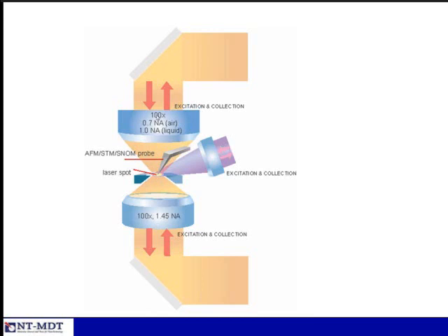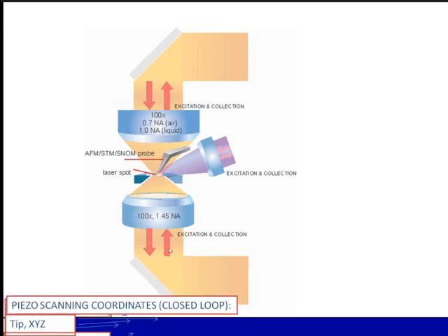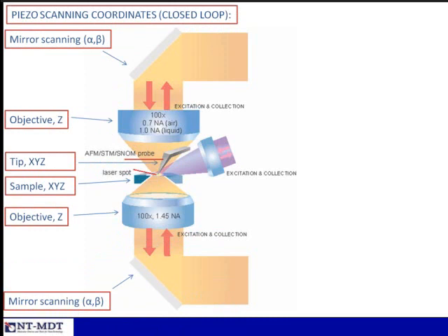The most universal configuration integrates AFM with multiple optical paths simultaneously. This existing system, working at several NTMDT customers, combines bottom illumination with NA up to 1.49 or 1.5, a top lens at NA 0.7 in air, and a side high-NA lens. The tip can be placed at the focal point of all three lenses, enabling any combination of excitation and collection: top excitation/bottom collection, side excitation/top collection, and so on. All scanners are closed-loop piezo scanners with nanometer precision and temporal stability.